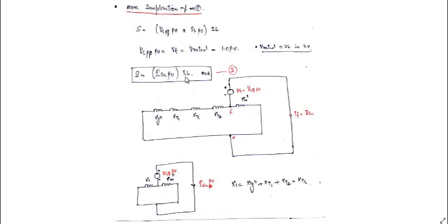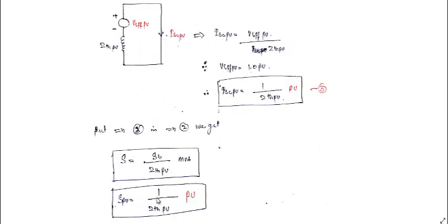That is this. So in per unit, S per unit will be equal to simply 1 divided by Z_TH per unit. This is the standard, or we can say the simplest, formula by which we can calculate the MVA rating of the circuit breaker in per unit. Then by simply multiplying the base MVA, we get the actual MVA of the circuit breaker.